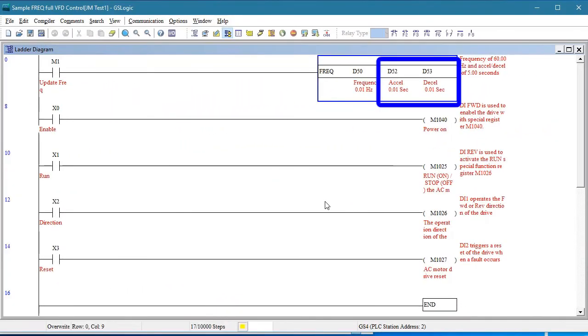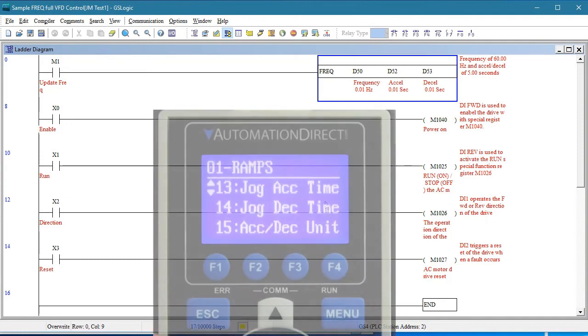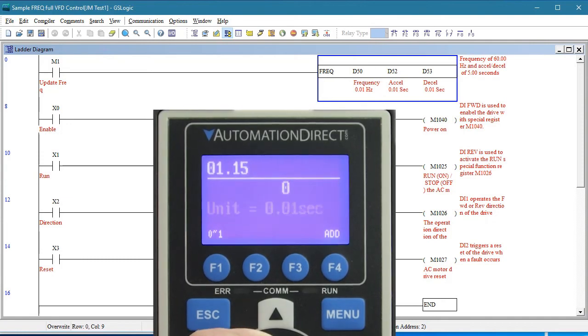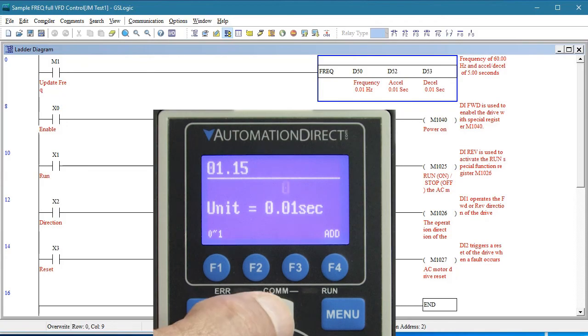We said earlier that these registers control the acceleration and deceleration and that they have two implied decimal places. Well, that's only for the default case. You can actually change that using parameter 1.15 from hundredths of seconds to tenths of seconds.